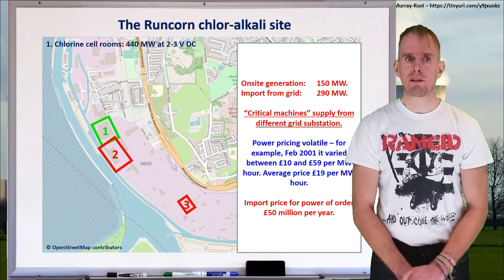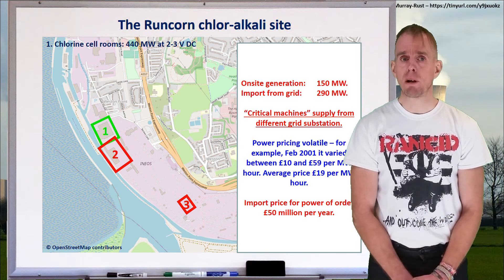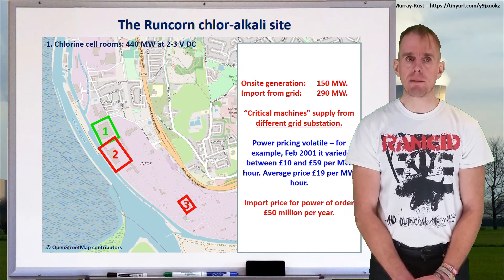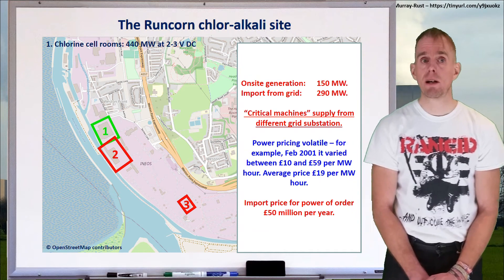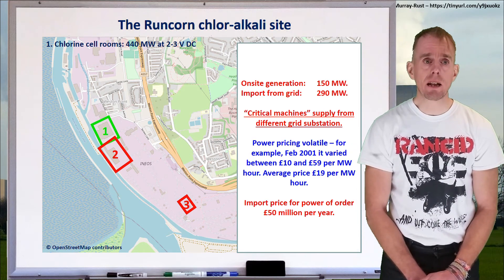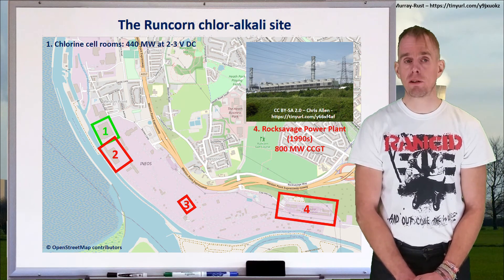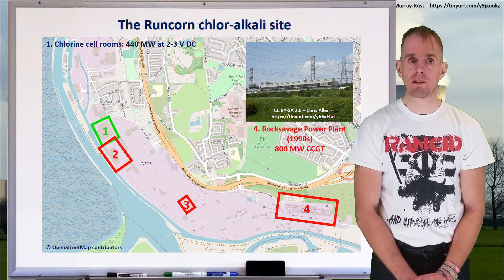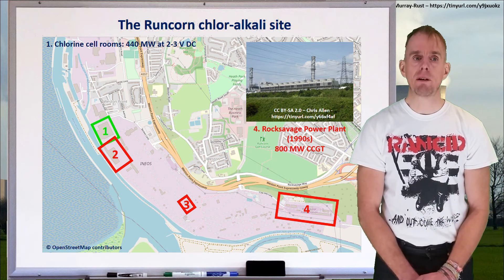Power pricing was the key challenge, being inherently volatile. In 2001, for example, the price of electricity ranged between £10 and £59 per megawatt hour, with an average of about £19 per megawatt hour — making the annual power import bill roughly £50 million. In the 1980s, planning permission for a nuclear power plant on site was refused. But in the late 1990s, a contract was entered with a company called Intergen, who built an 800 megawatt combined cycle gas turbine at the eastern end of the site — the Rock Savage power plant — which still exists today, providing the balance of power to the chlorine cell rooms and exporting the rest to the national grid.